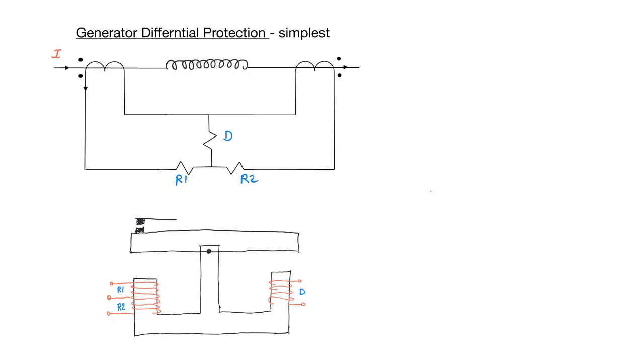Currents I_in and I_out should be equal under normal operating conditions — these are the primary currents seen by the current transformers. The secondary current from the first current transformer is called I1, and the secondary current from the second current transformer is called I2. Currents I1 and I2 flow out of the CT secondaries and into the differential relay.